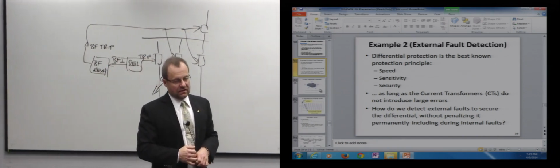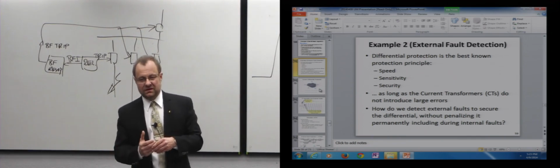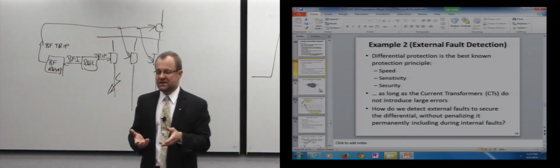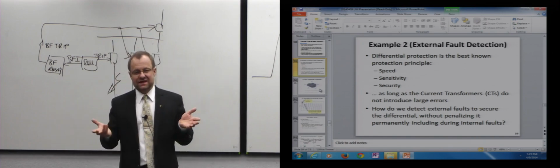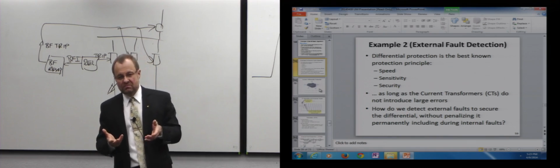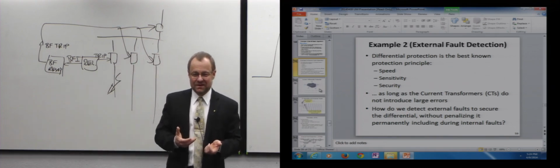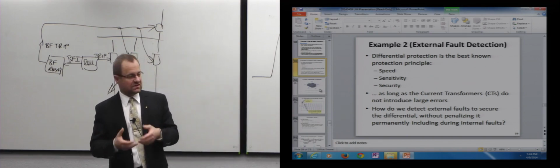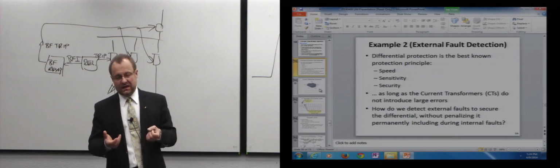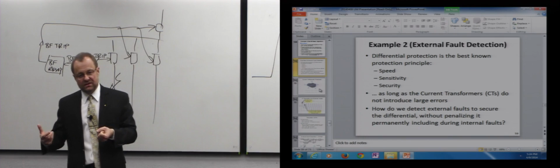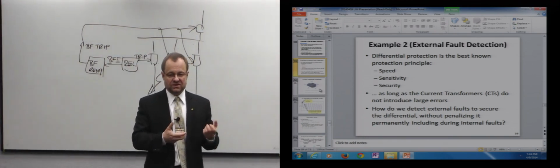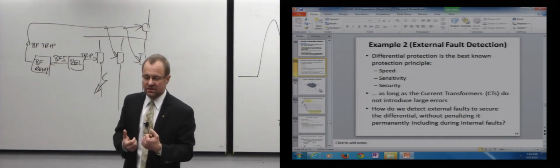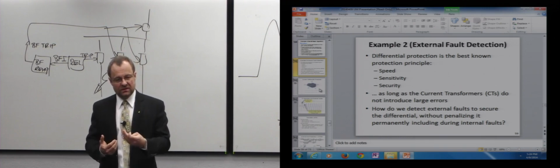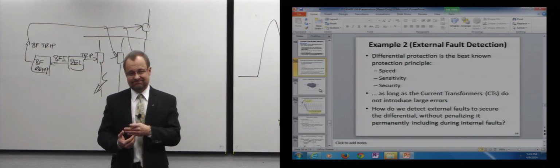Some people will say it's a CT saturation detection, and I typically ridicule that language because if the CT is saturated, why are you telling me this? I need to know before they saturate. When they saturate and you see symptoms of it, such as harmonics and what have you, it's already too late, unless you intentionally delay your tripping so that you could give your CT saturation algorithm a chance to pick up. We don't want to delay anything, so what we are doing is building an algorithm for external fault detection. We want to know that this is an external fault, and if CTs saturate, we want to be prepared for that before they saturate.